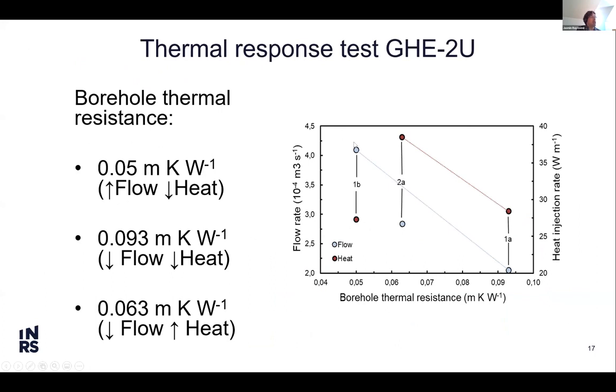You have the borehole thermal resistance as a function of flow and as a function of the heat injection rate. For a low flow rate and a low heat injection rate, the borehole thermal resistance increases. And for a low flow rate and a high heat injection rate, the borehole thermal resistance decreases, but not as much as when there's a high flow rate. So for these boreholes that are made with groundwater filling the hole, it's already known that if you change the heat injection rate, that affects the borehole thermal resistance, because the more heat you inject, the more natural convection you get in the ground, and the lower the borehole thermal resistance goes. But the impact of flow rate is a little bit unknown, and that's something we demonstrated here. The flow that you set has even more impact on the borehole thermal resistance than the heat injection rate.